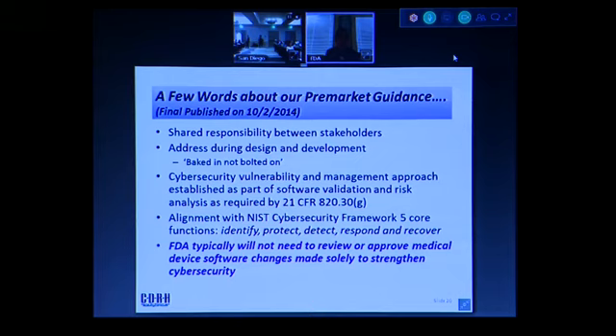Design inputs related to cybersecurity should be established for devices. Similarly, cybersecurity vulnerability and management approach needs to be part of the software validation and risk analysis, and that's required by 21 CFR 820.30(g). This is part of design controls of the quality system regulation. The guidance aligns with the NIST cybersecurity framework's 5 core functions. We discreetly call out those functions as identify, protect, detect, respond, and recover. And we encourage medical device manufacturers, as they look to their development, to adapt these 5 core functions as well.